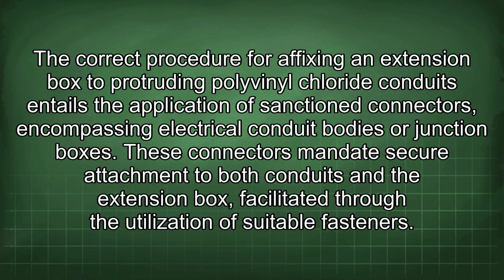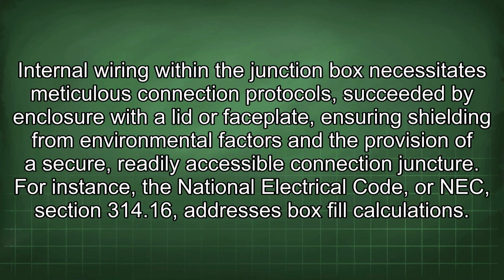The correct procedure for affixing an extension box to protruding polyvinyl chloride conduits entails the application of sanctioned connectors, encompassing electrical conduit bodies or junction boxes. These connectors mandate secure attachment to both conduits and the extension box, facilitated through the utilization of suitable fasteners. Internal wiring within the junction box necessitates meticulous connection protocols, succeeded by enclosure with a lid or faceplate, ensuring shielding from environmental factors and the provision of a secure, readily accessible connection juncture.